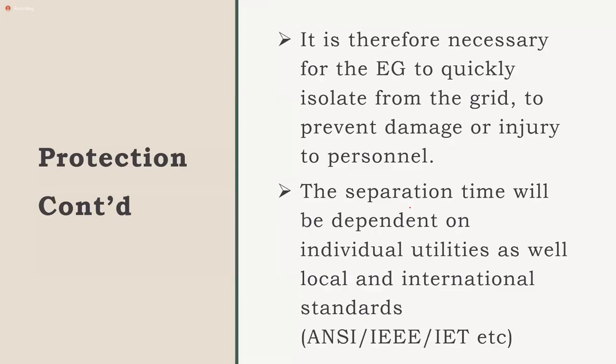And so, persons who are giving consideration to generating their own electricity and maybe selling it to the utility company, these are some of the checks and balances that the utility company will have to make before you are granted the license. So if you want to sell back to the utility, you'll have to get a license from the ministry. And part of that licensing process is that you have to show that you have the ability for quick disconnection should there be loss of power coming from the grid. So you are not then sending power back into your neighbor's home. Are we clear on that?